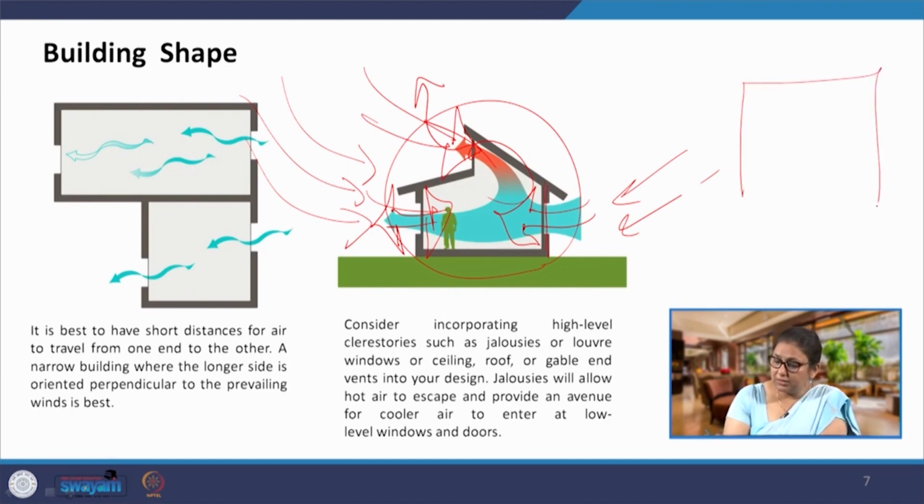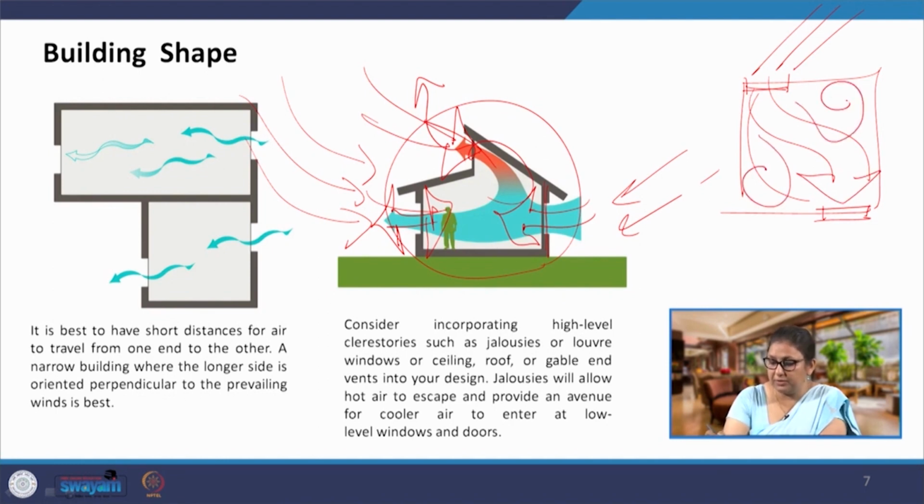We have seen earlier, suppose we have fenestration which has been provided on two opposite ends. Now, if we are looking at the windward direction, if it is like this at 45 degrees or perpendicular to the wind direction, it works. This is how the movement of wind is going to happen, with the remaining area getting eddies of the ventilation.